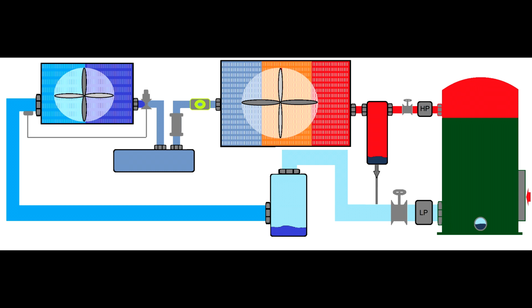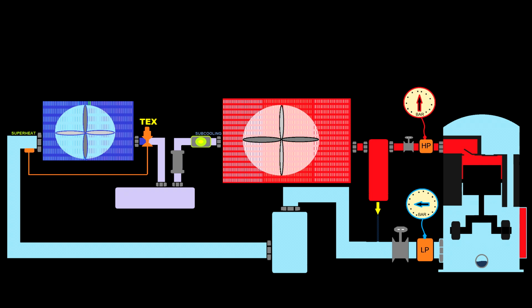store. But one engineer who made a mistake tried to convince me that the compressor generates enough heat, so I don't need another source of heat in the store. Look at this compressor, you'll see that the piston is moving, and what the engineer, or the designer, thought in his head is that the compressor will generate the extra heat required to heat the store if the refrigeration equipment wouldn't have a lot of demand. And guys, we all know we try to build efficient compressors not to have mechanical heat, because this is acting against us. These compressors are not designed to create heat for a heat recovery system. Otherwise, the efficiency wouldn't make sense.